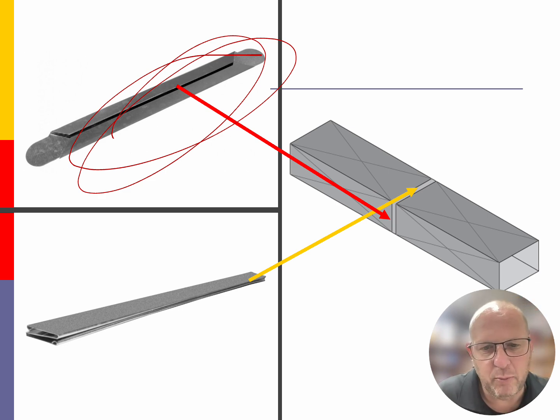Some people, after they get done doing that, will put screws in the top of those, and that's just going to firm up that drive cleat and its connection to the ductwork itself. I recommend not to do that. I've actually seen ductwork separate from doing that, especially if you're putting it on the shorter side of the ductwork. I would stick with the drive cleats, bend them over, and then we'll talk later about how we're going to seal that individual joint, because that is not an airtight seal.